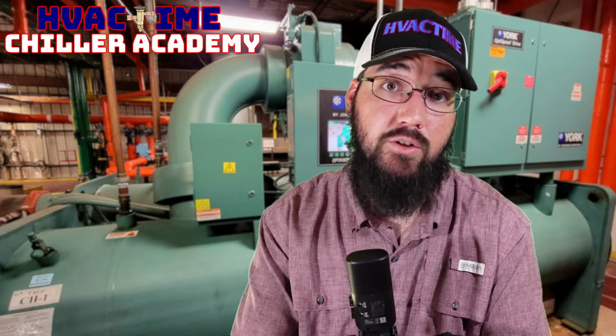So when you get into much larger machines, you'll have a water box with a hingeable door. Smaller machines, they'll just be a set of pipes connected to the end of a compact water box, as it's referred to, or an end bell with the water connections. Usually on those smaller ones, we're not going to open the piping side. We're just going to open the other side where there's no pipes at all.